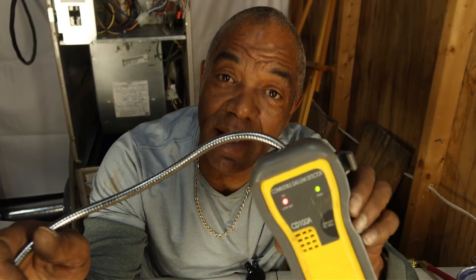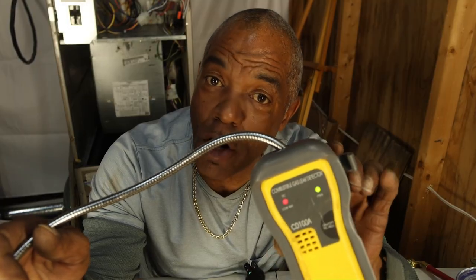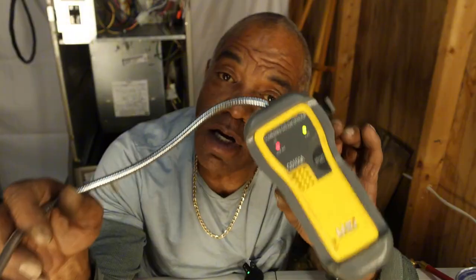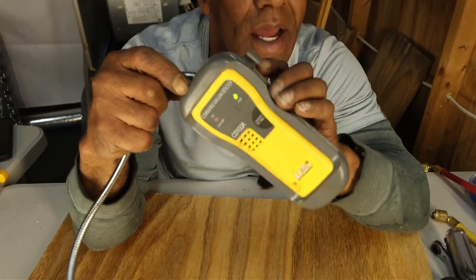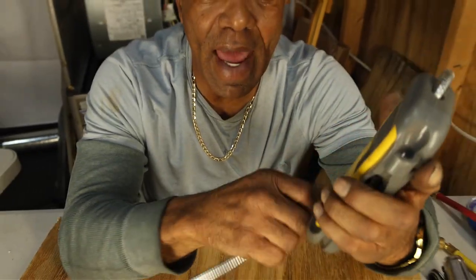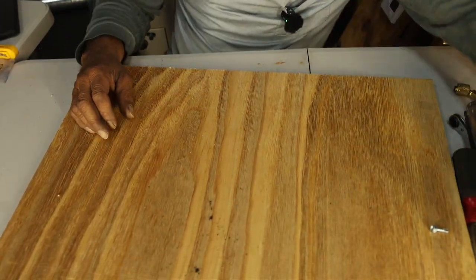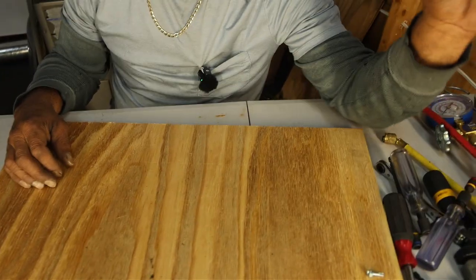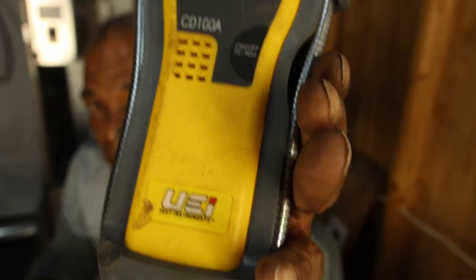Okay? But you get it to a certain set point and you leave it there with just a heartbeat, and then you look for leaks in our freon, leaks in gas, carbon monoxide leaking into the house. Awesome tool. A service tech is really going to do well to have one of these. All right. It's a gas leak detector. And multiple vendors make them, multiple styles. This is just the one that I purchased, which is the UEI version of this system.